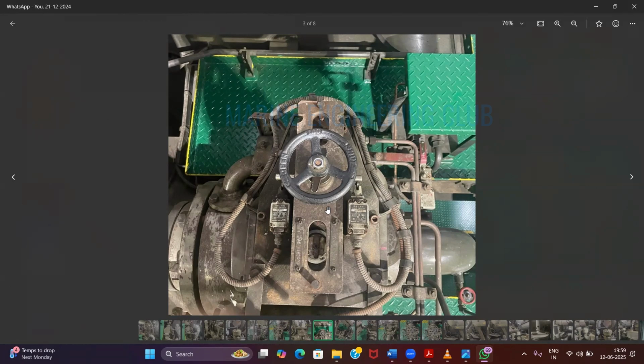Just like how the turning gear is turning. Okay, little faster than turning gear, obviously, but not as fast as when you give 30 bar. So if any restriction comes, this air will not be able to turn your engine. And for a particular time period, if the engine has not completed one revolution, then it will shut off and it will give an alarm. सर तो मतलब वो 30 बार वो सेम रहेगा.